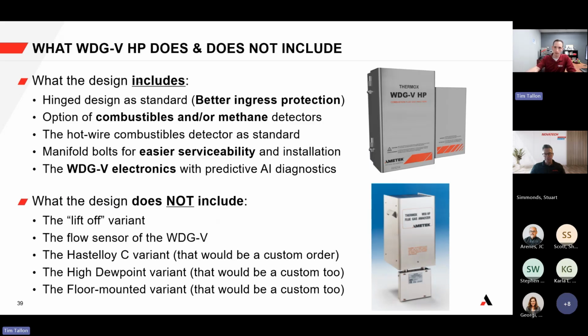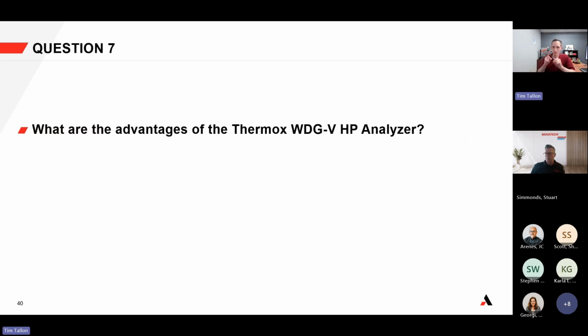There's a better enclosure for the WDG-V HP, with better ingress protection, keeping it working in those cold areas in Canada, like you mentioned, and protecting it from the elements. Again, combustibles and methane are standard options. The hot wire detector is always standard for severe service, even high sulfur applications. There's greater serviceability with the WDG-V electronics. It does not include the lift-off version or the flow sensor. We can certainly make versions for Hastelloy C for highly chlorinated applications and high dew point versions as a custom. We've done a number of those already, and also floor mount variants if you need them for a nozzle on the floor. That's what's new and what's included. I hope that answered your question.